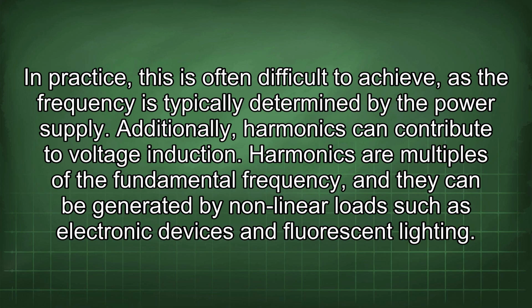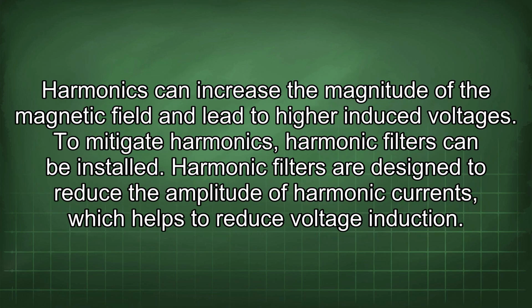Additionally, harmonics can contribute to voltage induction. Harmonics are multiples of the fundamental frequency, and they can be generated by nonlinear loads such as electronic devices and fluorescent lighting. Harmonics can increase the magnitude of the magnetic field and lead to higher induced voltages. To mitigate harmonics, harmonic filters can be installed. Harmonic filters are designed to reduce the amplitude of harmonic currents, which helps to reduce voltage induction.